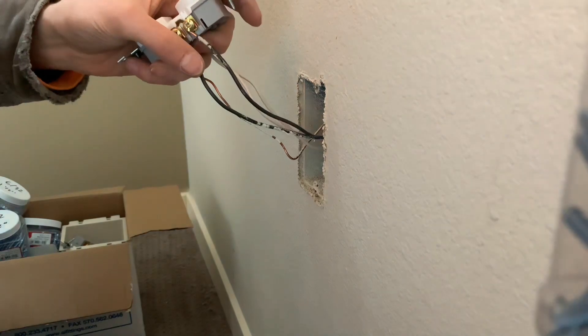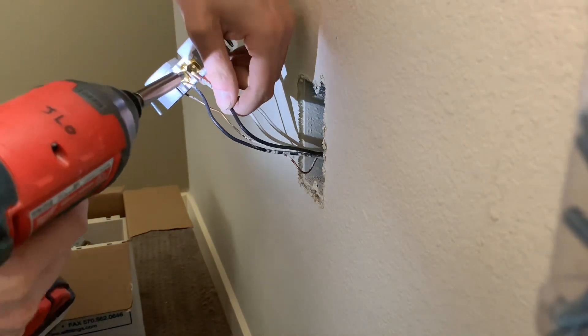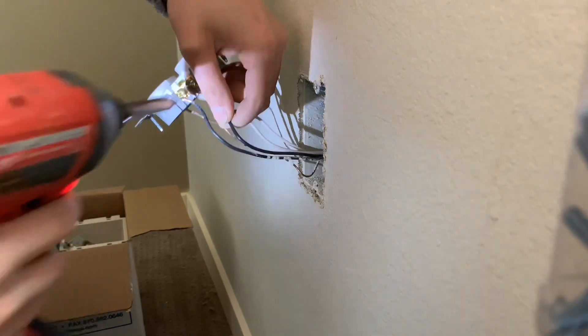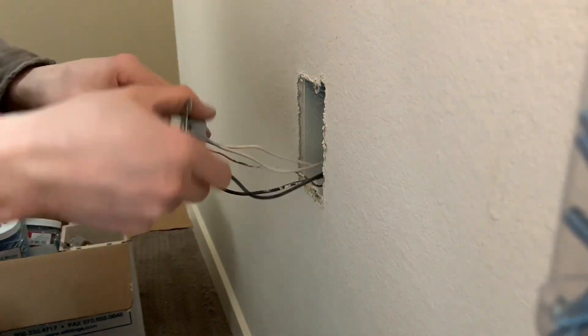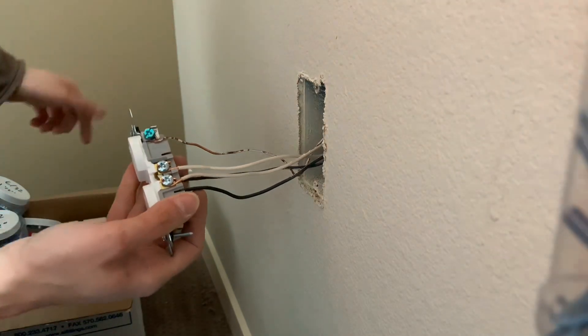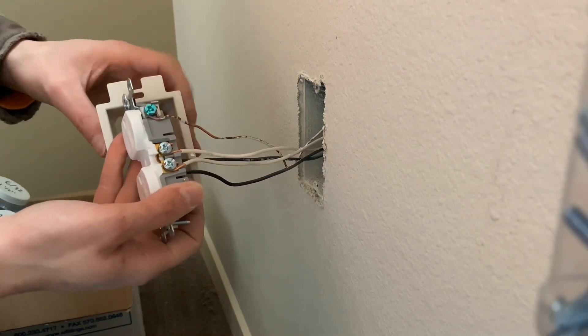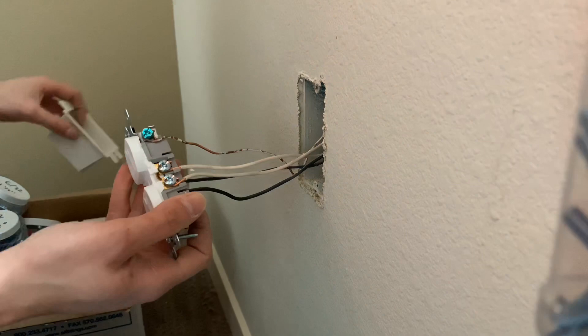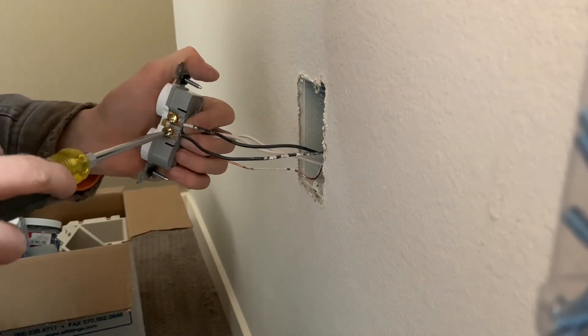Keep the wires inside the loops. I'm doing a lot of plugs right now, and I don't know if it was the last company here before we took over this job, but a lot of these wires aren't even tight — they're all overlapping and messy. Especially when the ground wire is coming out, trying to put a box extension on becomes a nightmare when that wire catches on the edge.